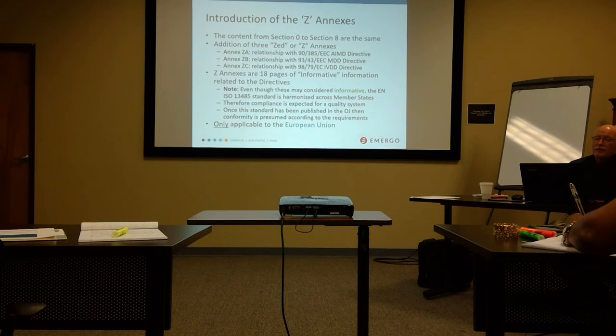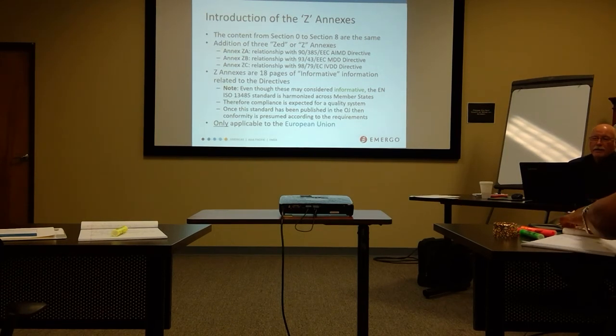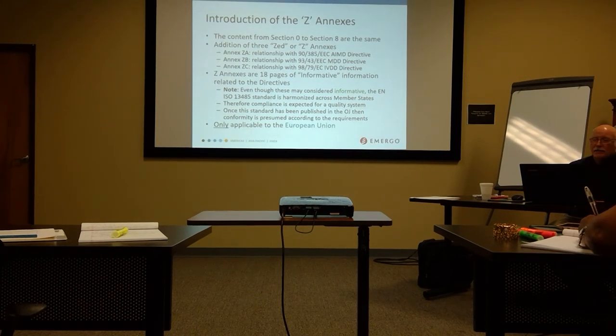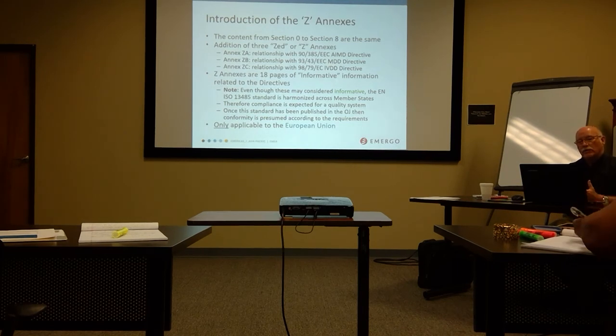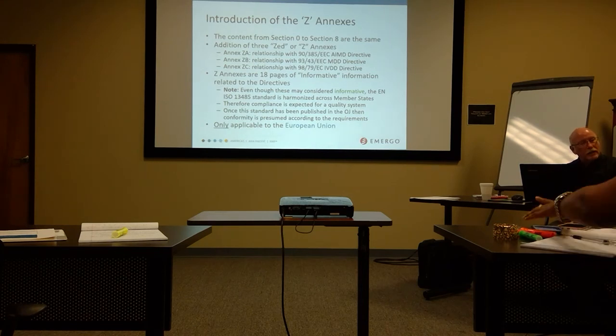The EN version of this thing is identical to the non-EN, with the exception that they added 3 of what we call the Z annexes. And what they did in the Z annex is tie 13485 more tightly to the parent directives. There are 3: the Active Implantable directive, which is going away by the way, the MDD, and the IVDD. These are informational - there's nothing in there that's a must-do, but they're a way to coordinate ISO back to the product. Remember I said at the very beginning, quality is independent of product - this is a way to kind of tie those two things together. It is only appropriate and applicable to the EU. Does not exist in the US.